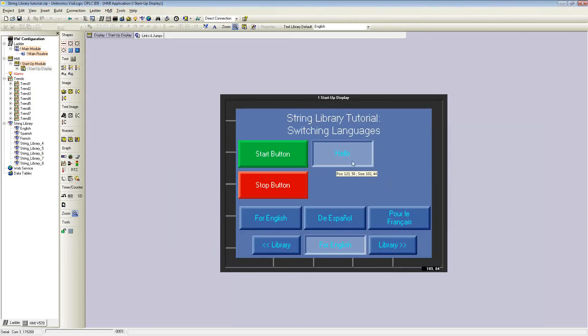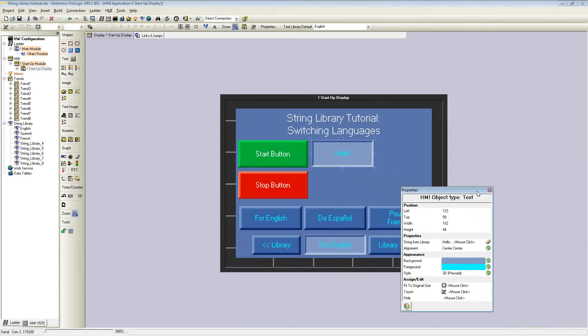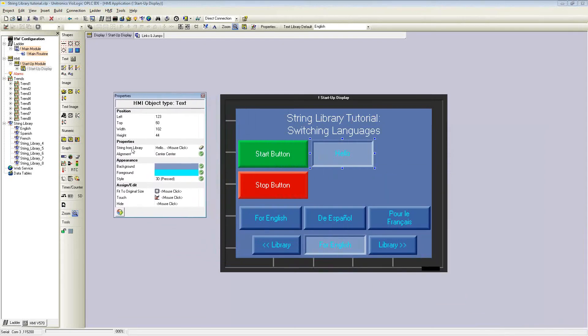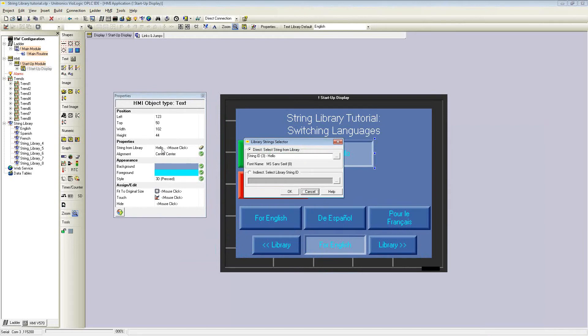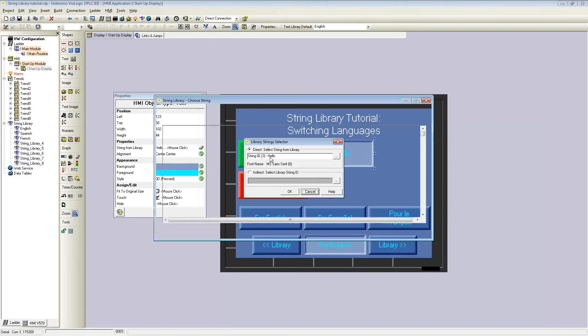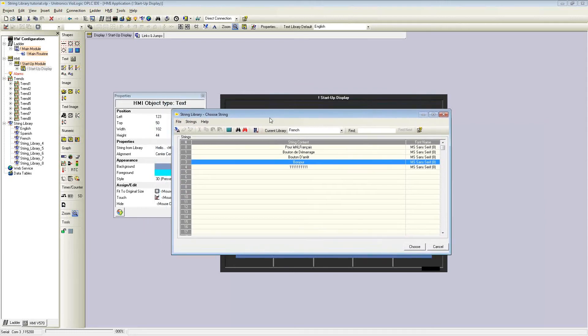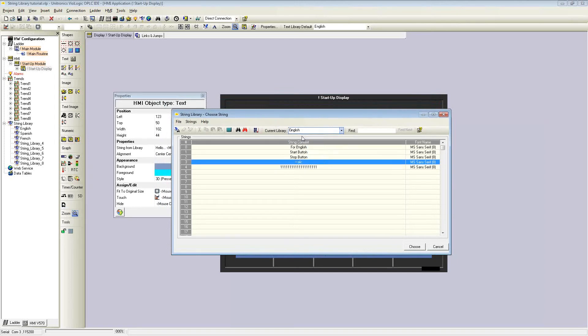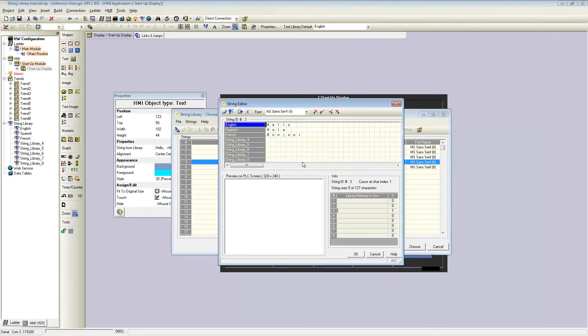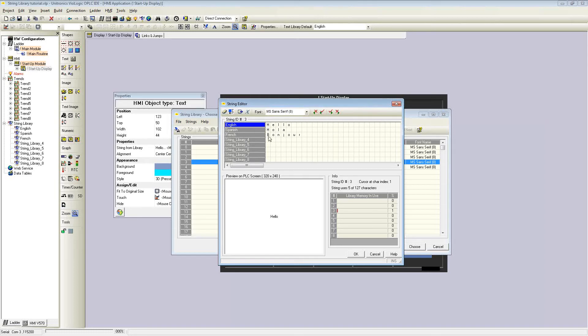As shown before, there was a text box here. Once the text box properties is opened, I selected string from library. This then prompted me to select a direct or indirect library ID. I selected string ID 0, string ID 3. This brings up the string library selection window. Here is the French library, but I can switch to any library I wish. I selected library 3. As you can see, string ID 3 on English will display as hello. In Spanish, it will say hola, in French, bonjour.